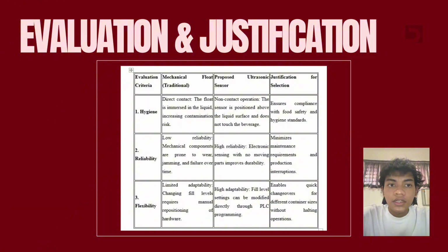Second, reliability. Mechanical systems are susceptible to wear, jamming, and hardware failure. Because the ultrasonic sensor is entirely electronic with no moving parts, we significantly minimize maintenance needs and prevent unexpected production downtime. Finally, flexibility. If we need to change bottle size with the float, we would have to manually reposition the hardware. Our system allows for high adaptability. We can modify fill level settings directly through the PLC programming, enabling rapid changeovers without halting operation. This selection ensures the system is not only cleaner, but significantly more durable and versatile.